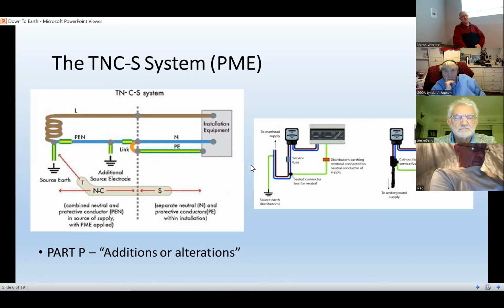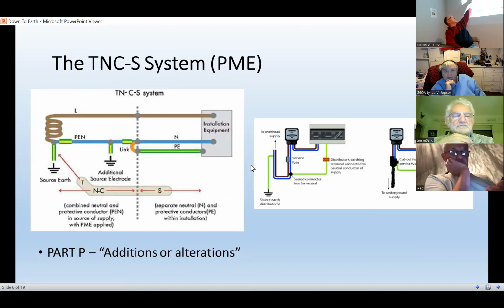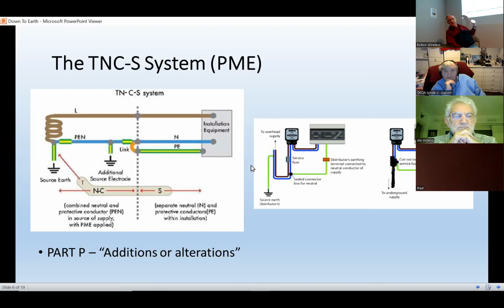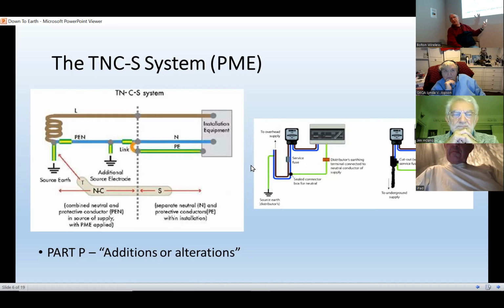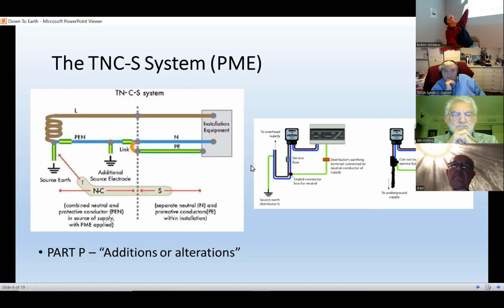So basically what that's saying is, at the generator end, you don't have an earth connection, you have a PEN, protective earth and neutral. So the earth and the neutral are combined there. And when it comes into your house, they break it out again and give you a neutral connection and a separate earth connection. So as far as you're concerned, when you look in your meter cupboard, you think this is normal, I have an earth wire, but you don't actually have an earth wire. It's actually fed through the neutral from the supply.